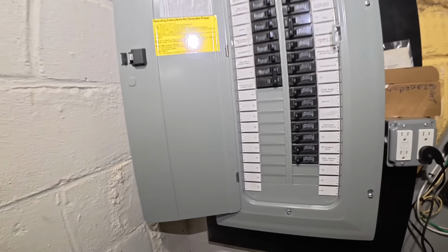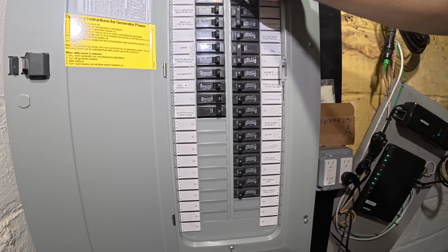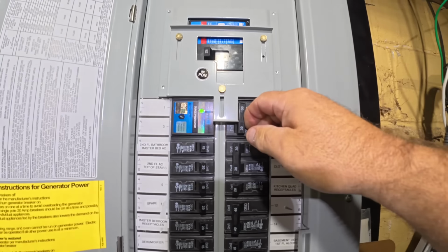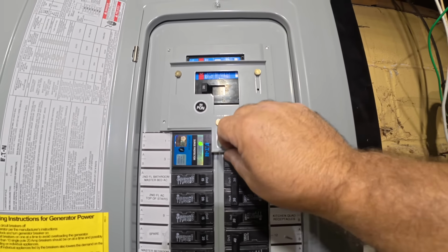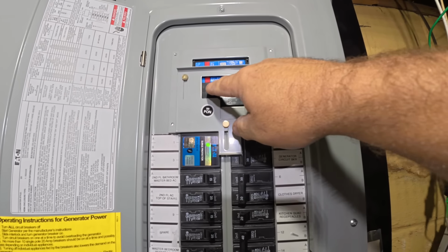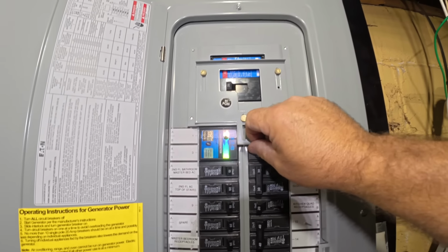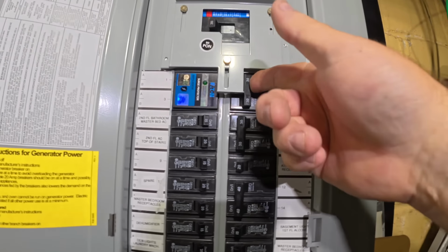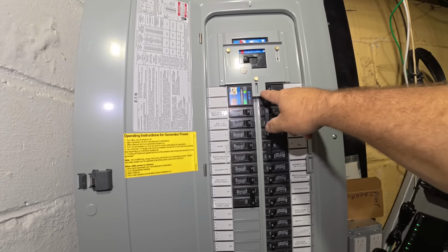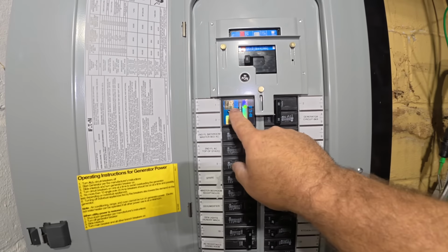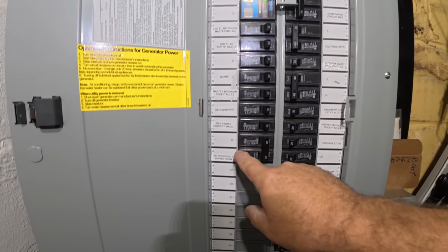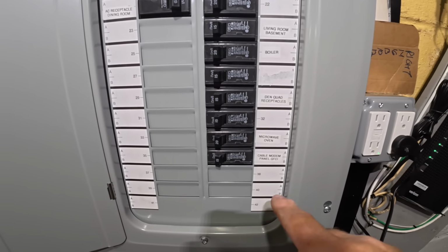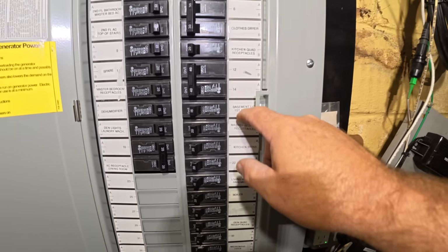Okay, so now that the interlock is in, you see, we cannot raise this up. We cannot turn on the 30 amp circuit breaker. All right, if we can't raise this up, we'd have to turn off the main, then we could slide up the interlock to turn on the generator breaker. So this interlock is doing exactly what it's supposed to do. And here's our whole house surge protection, and then we labeled all the circuits before we left on Saturday.